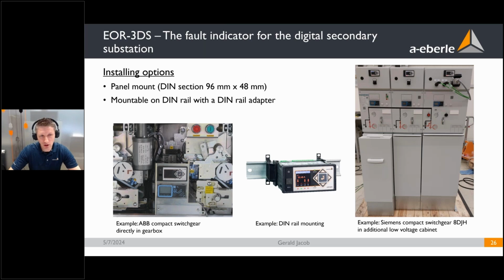Regarding the installing options, of course, this device is meant to be installed in compact switchgear stations, as you can see, for example, on the left side and on the right side. On the left side, this is one of ABB without the front plate of the compact switchgear station. And as you can see, there is a frame just above an empty frame just above the VDS system, where you can install this device, EOR-1DS or EOR-3DS.